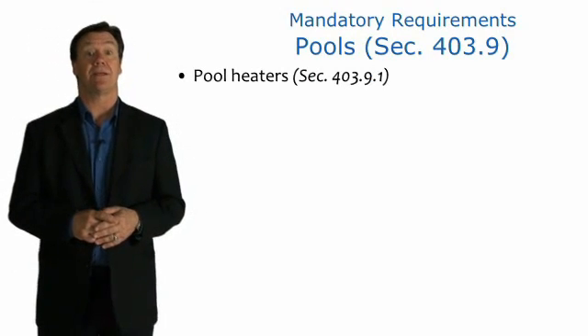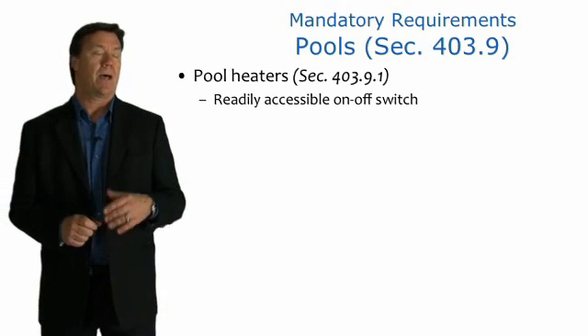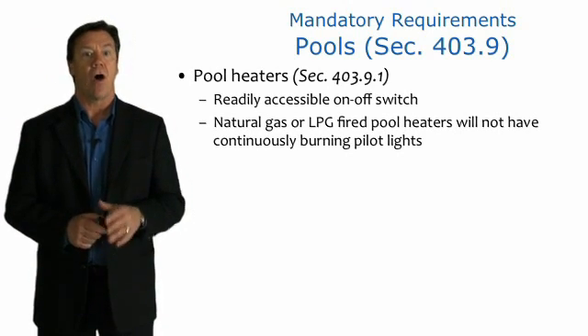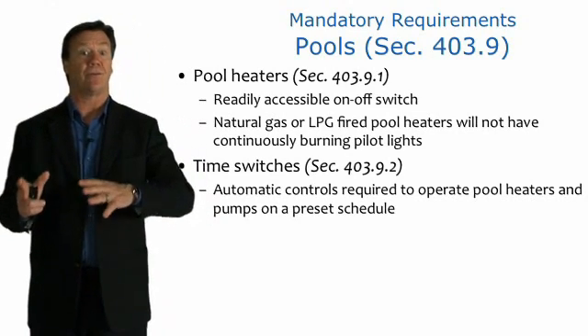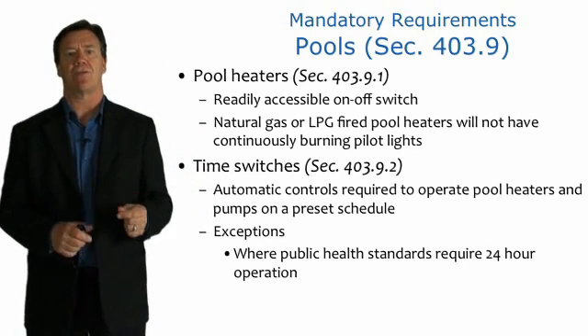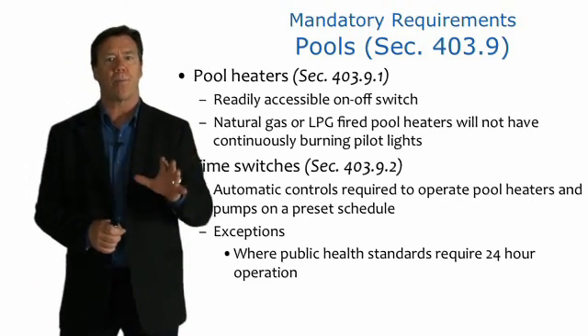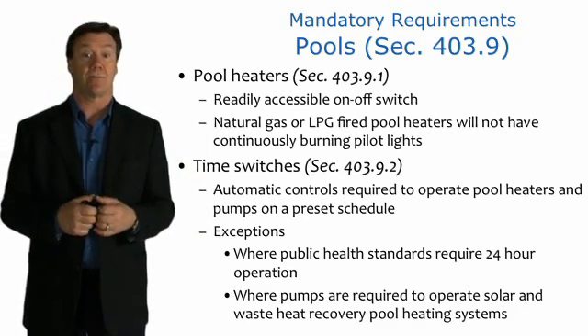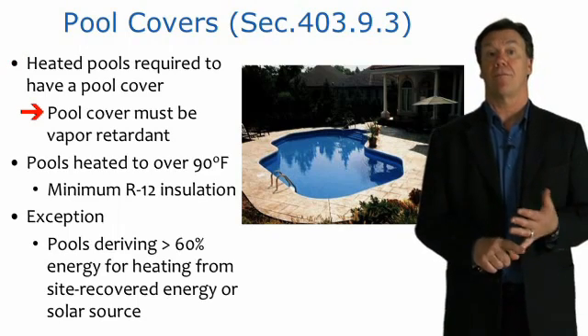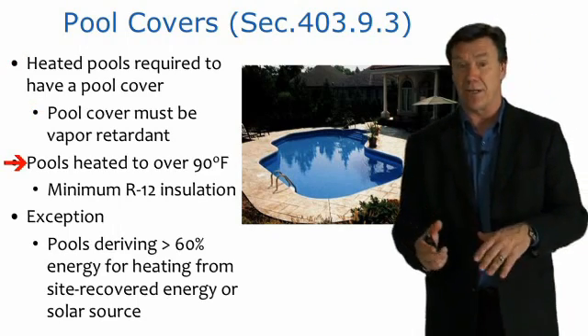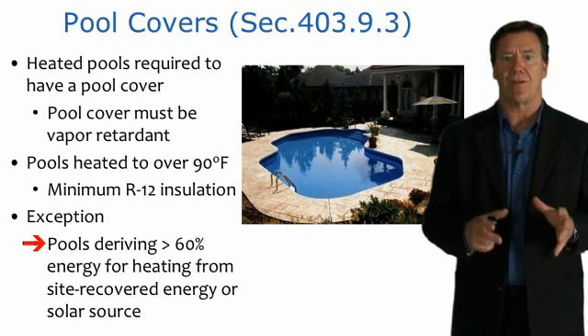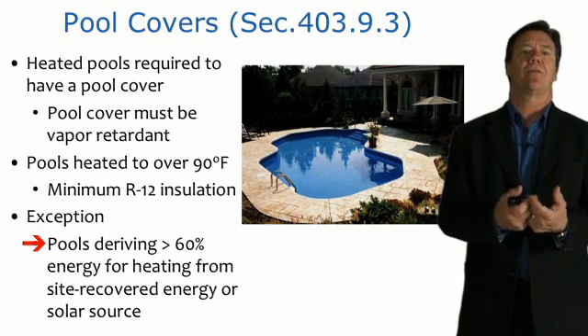For pools, there must be a readily accessible on-off switch, and natural gas or LP fire heaters cannot have continuously burning pilot lights. Pools must also have time switches and automatic controls to operate heaters and pumps on a preset schedule — exceptions apply where public health standards require 24-hour operation or where pumps serve solar or waste heat recovery systems. Pools must have a vapor-retardant cover, and pools heated over 90 degrees require a minimum of R12 insulation, except for pools deriving more than 60 percent of their heating energy from site-recovered or solar sources.